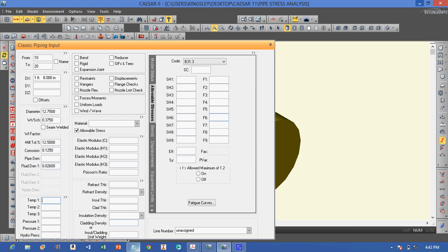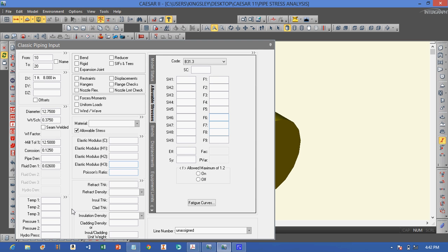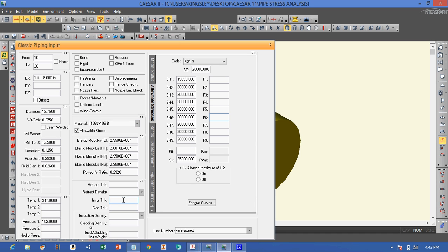The temperature is 347 degrees Fahrenheit, and the pressure is 152 PSI. The material is A106B, the insulation thickness is 2 inches, and the insulation material is calcium silicate.